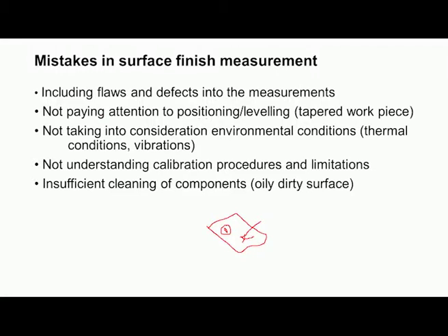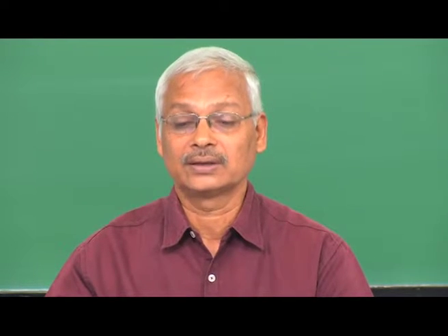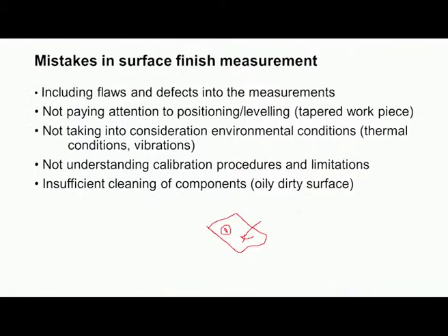Then not paying attention to positioning and leveling of the workpieces. So positioning of the stylus on the workpiece and the leveling of the stylus on the workpiece are very, very important. If we do not level the stylus or the probe onto the surface properly, then we will get erroneous results. So this is very important in the case of tapered workpieces.